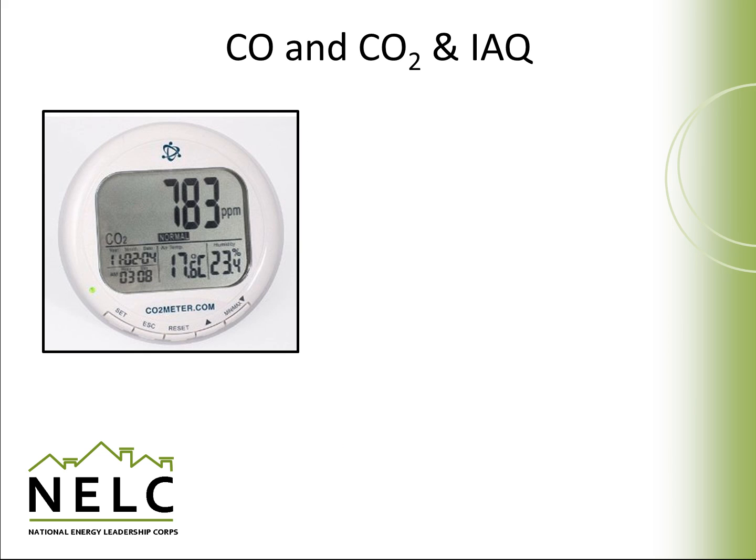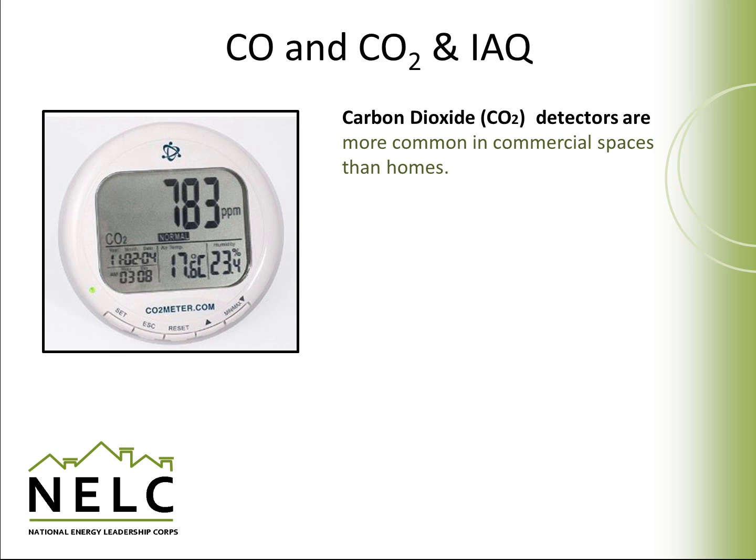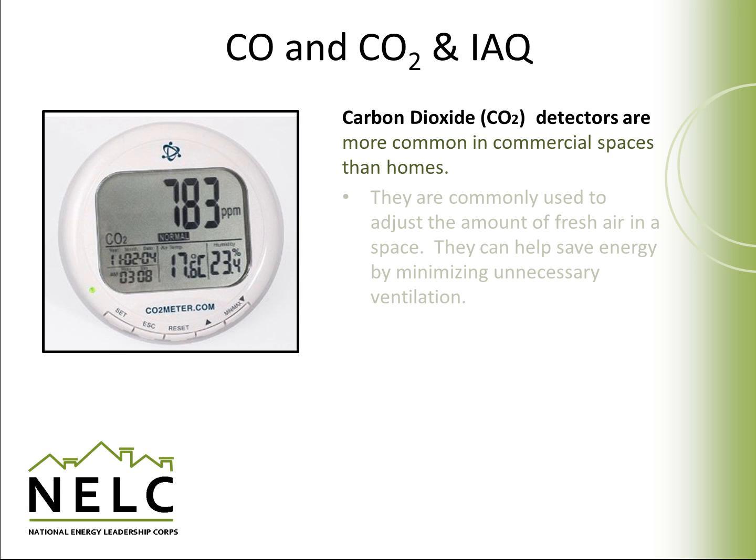A simple way to monitor carbon dioxide levels is to use a carbon dioxide detector. Some detectors are available that sense both carbon monoxide and carbon dioxide. In modern buildings, CO2 detectors are used in potentially crowded spaces. If a buildup of carbon dioxide is detected, they can trigger an increased amount of ventilation into that space. This can help save energy because they're only introducing the right amount of fresh air that we actually need and can avoid unnecessary ventilation that can add to heating and cooling costs.